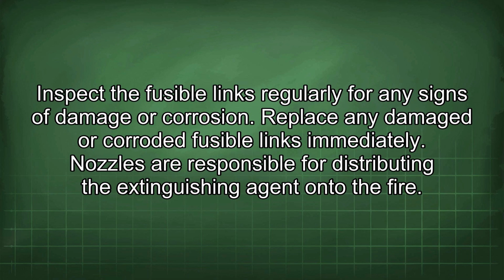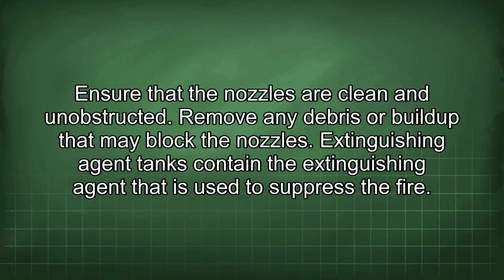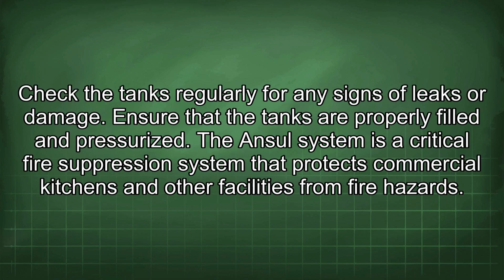Nozzles are responsible for distributing the extinguishing agent onto the fire. Ensure that the nozzles are clean and unobstructed. Remove any debris or buildup that may block the nozzles. Extinguishing agent tanks contain the extinguishing agent that is used to suppress the fire. Check the tanks regularly for any signs of leaks or damage. Ensure that the tanks are properly filled and pressurized.